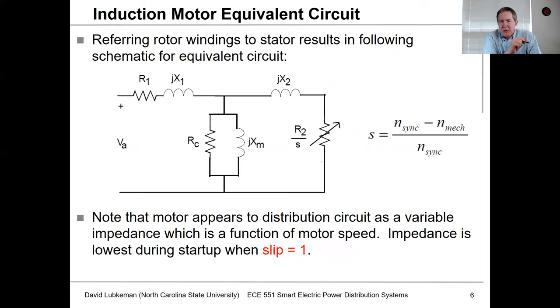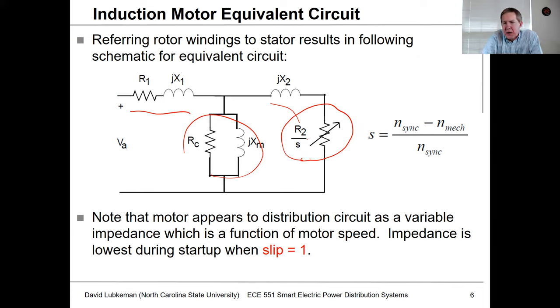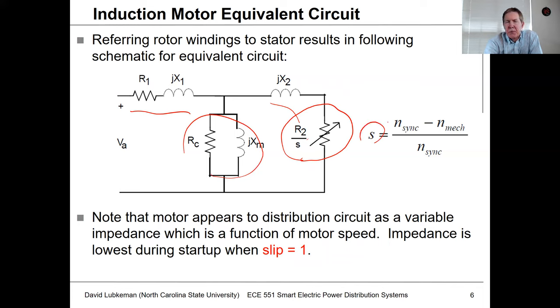The model for this machine is very similar to a transformer. We've got a model for the stator, a model for the rotor, a model for the magnetizing reactance X_M, and a model for core loss. What's different in this case is that the resistive part of the circuit on the rotor side is given by R2 over S. This represents the amount of power going to the mechanical load hooked up to the motor. Normally in steady state, slip is about 0.03, making this resistance rather large and dominating the whole impedance.